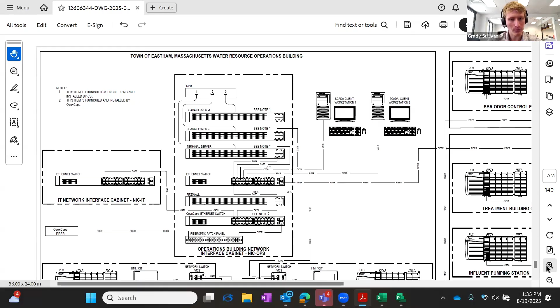So we have SCADA server 1 in the rack, SCADA server 2, and terminal server. The terminal server allows for multiple independent connections, while the other SCADA servers allow for basically a one-to-one mapping for those SCADA client workstations. So that basically gives us the brains of the whole SCADA system and how it pulls data from those other PLCs.